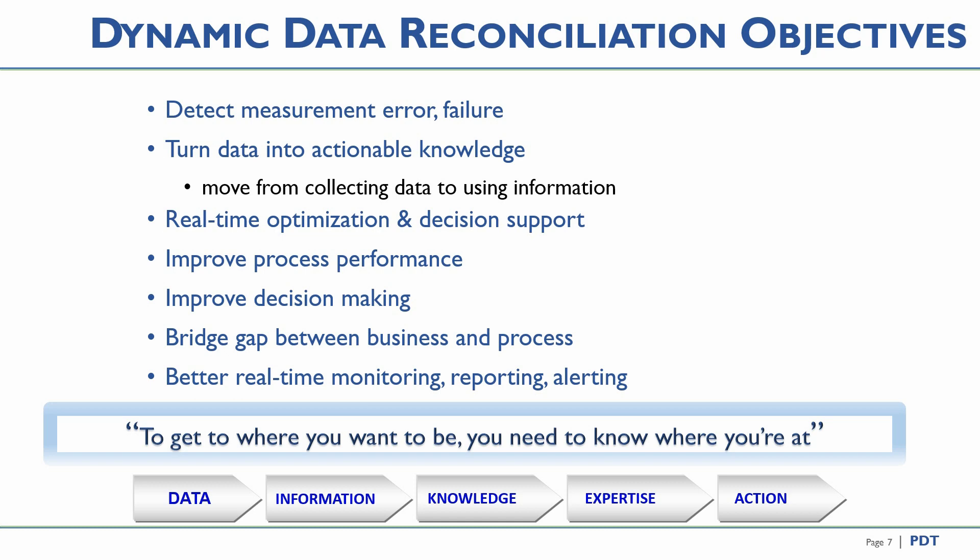In order to take reasonable process action, one needs to know where the process is currently operating without being fooled by measurements that do not add up. Dynamic data reconciliation fits a first principles model through the data to detect and correct measurement error by trying thousands of trials each minute. Making sense of the data moves the bar from collecting data to understanding the current process operation. This supports suitable actions such as better process decisions, accurate real-time optimization, and better monitoring, reporting, and alerting.